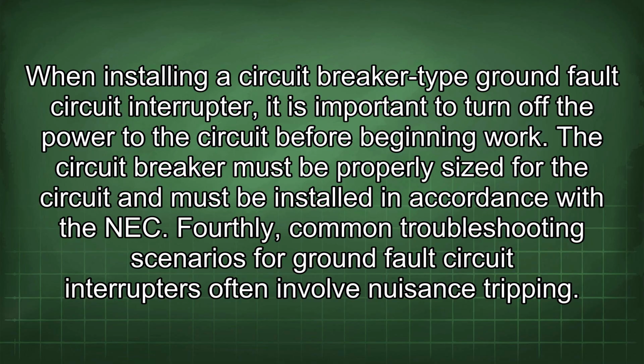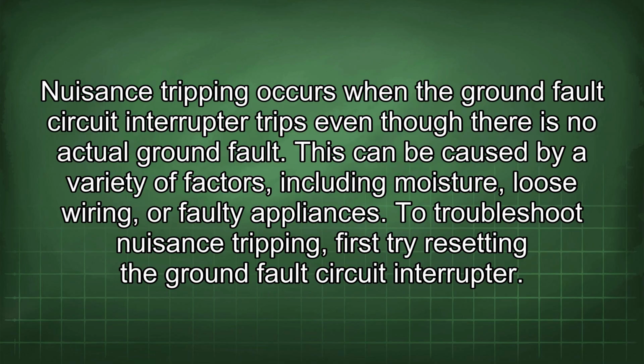Fourthly, common troubleshooting scenarios for ground fault circuit interrupters often involve nuisance tripping. Nuisance tripping occurs when the ground fault circuit interrupter trips even though there is no actual ground fault. This can be caused by a variety of factors, including moisture, loose wiring, or faulty appliances.